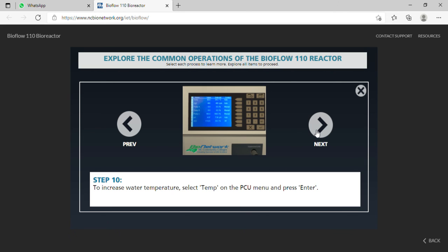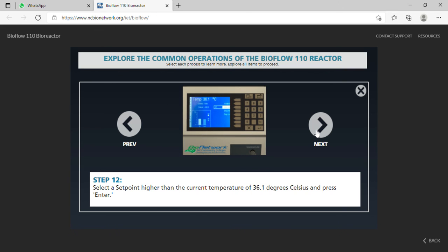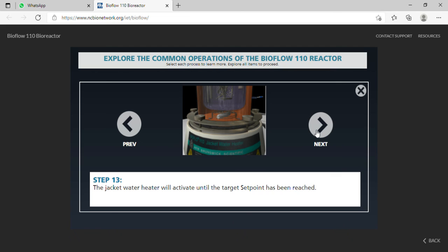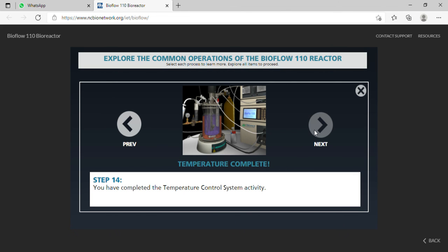Step 10. To increase water temperature, select Temp on the PCU menu and press Enter. Step 11. Select Setpoint on the PCU. This will take you to the Setpoint menu. Step 12. Select a setpoint higher than the current temperature of 36.1 degrees Celsius and press Enter. Step 13. The jacket water heater will activate until the target set point has been reached. Step 14. You have now completed the temperature control system activity.